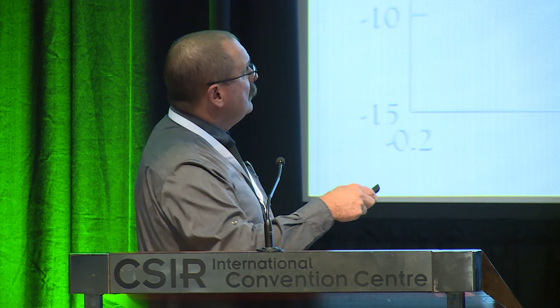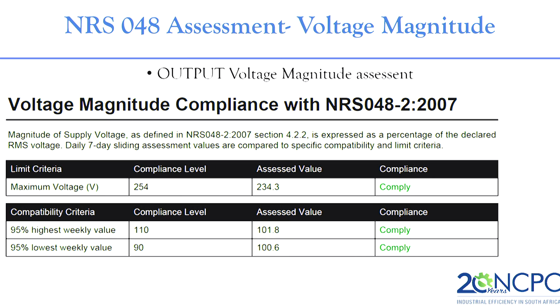This is just to show - this is not bad voltage regulation. There's a technical standard to tell you how good voltage is, but assessed over a period of time it changed roughly 6%. Not too bad, not wonderful, but acceptable. But look here, on the output of the device, not even 1%. So you can really keep the voltage perfect.